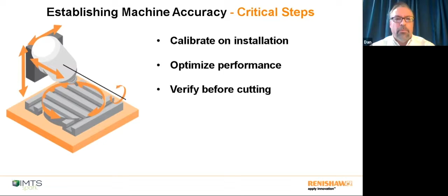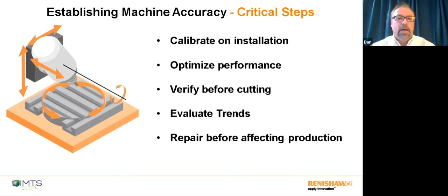Verify that before cutting every time. Before you start cutting, make sure the machine condition hasn't changed. Evaluate trends - make sure you're monitoring trends in machine capability, so you can repair or tune the machine before movement away from the calibrated accuracy affects your production. These steps need to be followed; they're absolutely critical as a foundation.